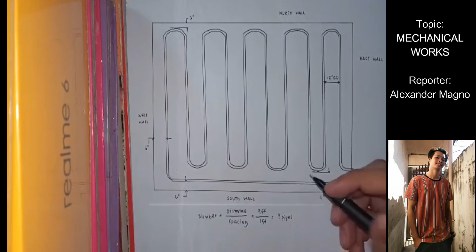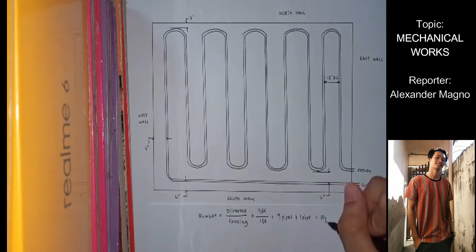In the standard, the number of pipes that run must be an even number for the supply and return to enter the room at the same point. So, if the number of pipes calculated is odd, we must add 1 to make it even. Plus 1 pipe. So the overall number of pipes that run along north and south is 10. After that, we must determine the length of the pipes needed for this heating system.